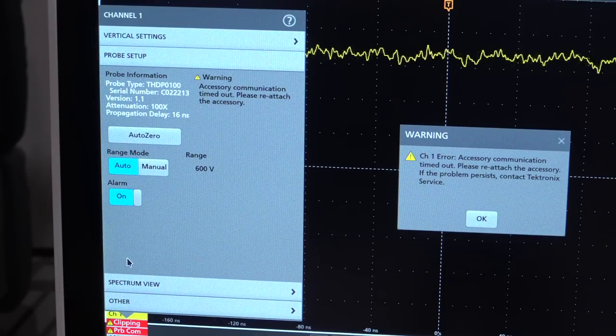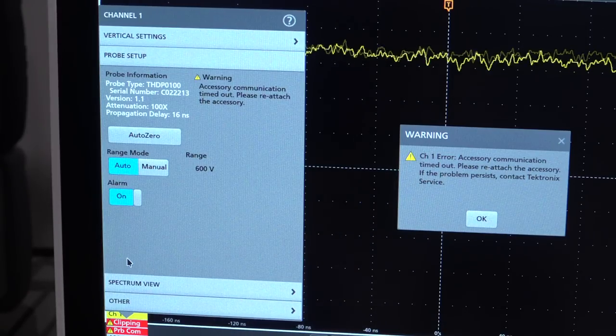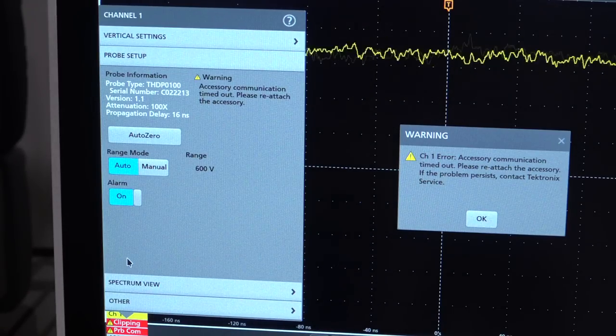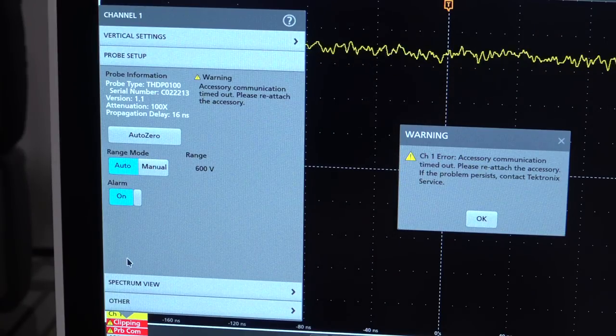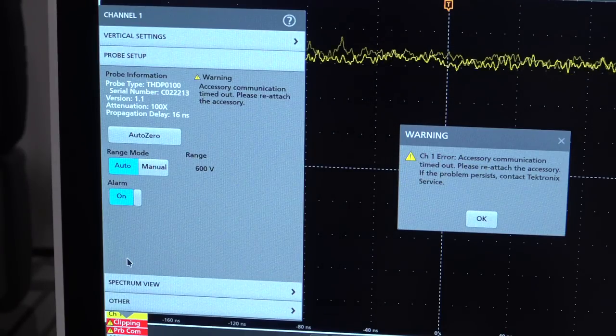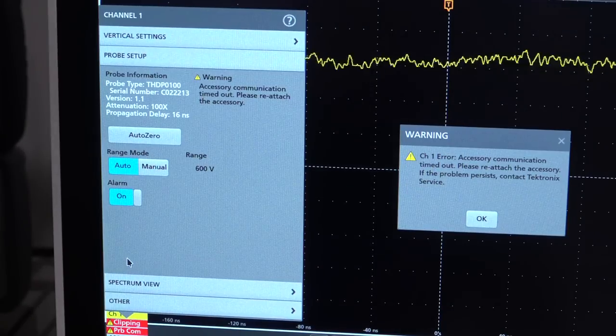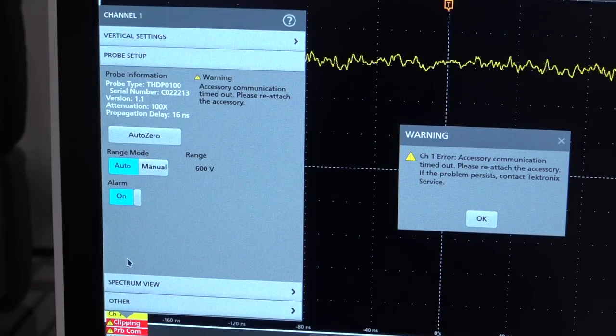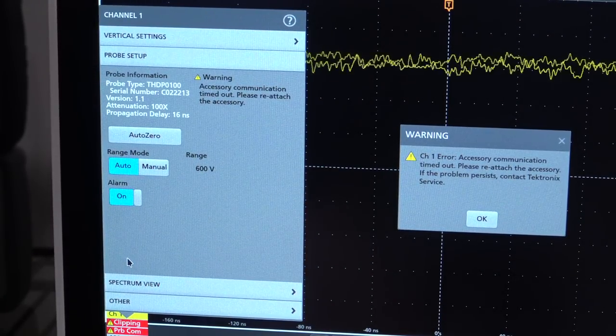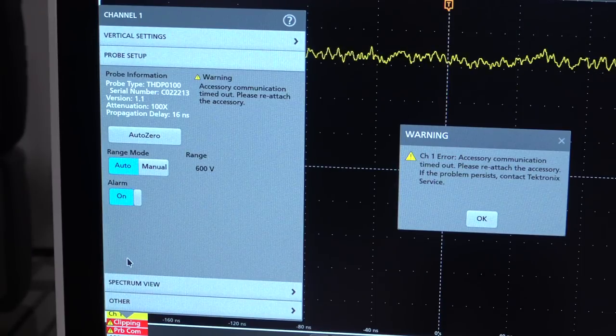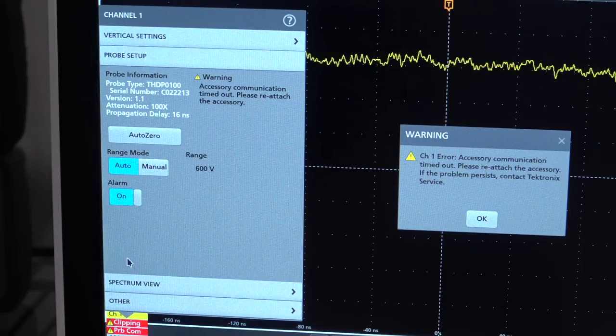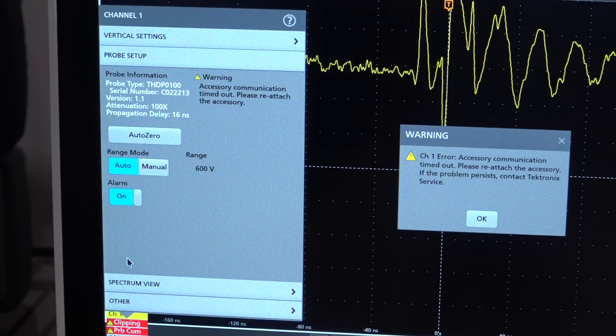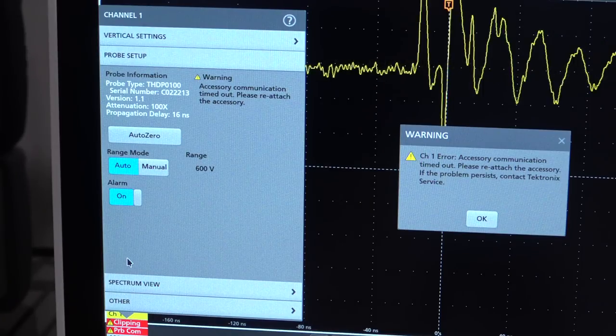It's actually frozen for some time before it gets to this point. It basically says that the communication has failed. These probes have some pretty sophisticated microprocessor controllers built into them and they do the communication to the scope. Obviously something's gone wrong, so either the firmware is corrupted or something's wrong with the IO. This also reports a serial number. The serial number written on the probe is C022213, and that is correct. It returns the correct serial number, just the wrong model number.